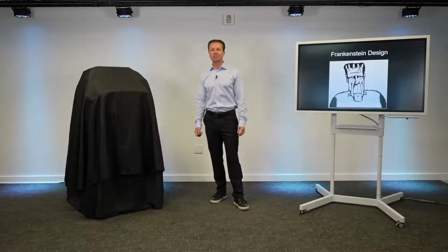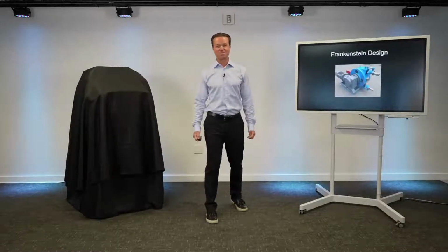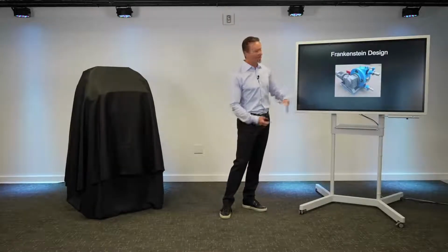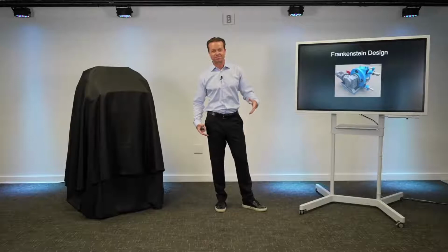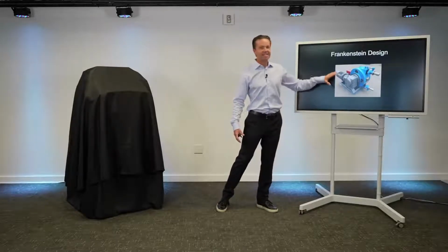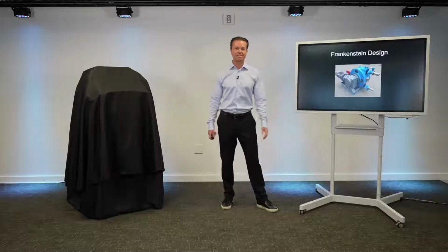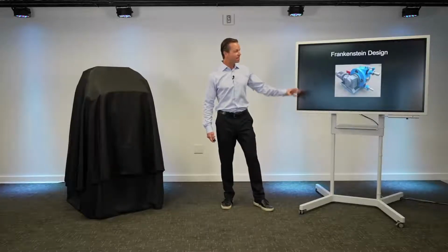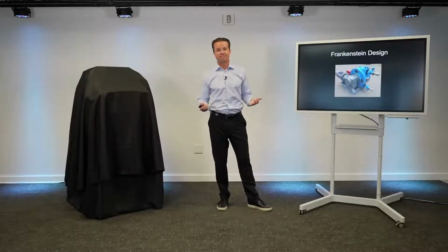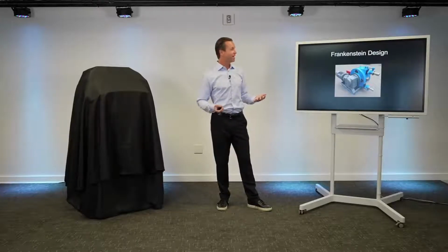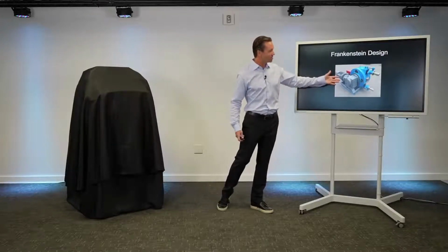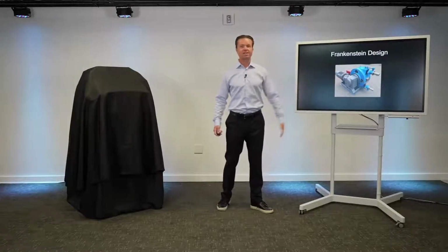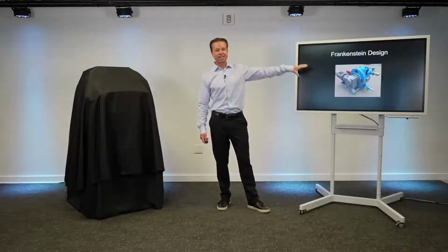The first design that we saw in the field was what we call the Frankenstein design. Let me show you really what I mean by that: it's a large pump head, and then you have your AC motor bolted to the pump head. You can't really do anything with that alone — then you need a power supply, a variable frequency drive, and a controller, and those get bolted onto the motor, the pump head, or somewhere nearby.